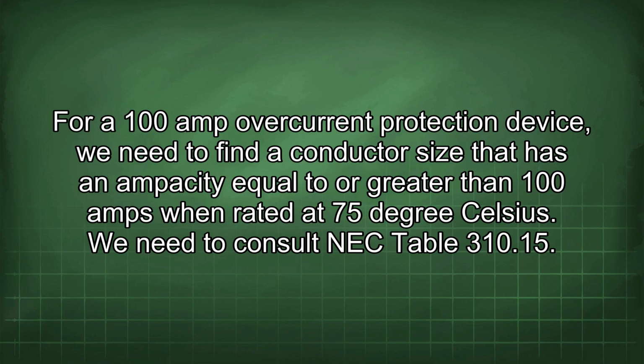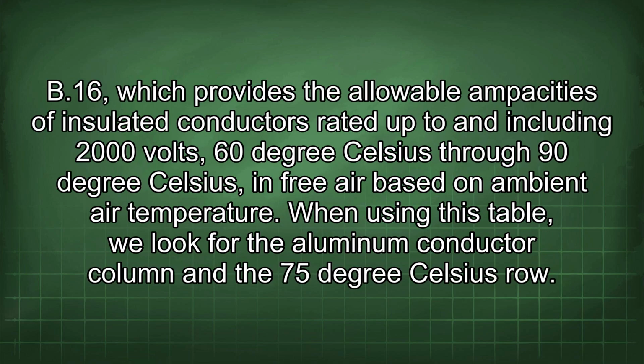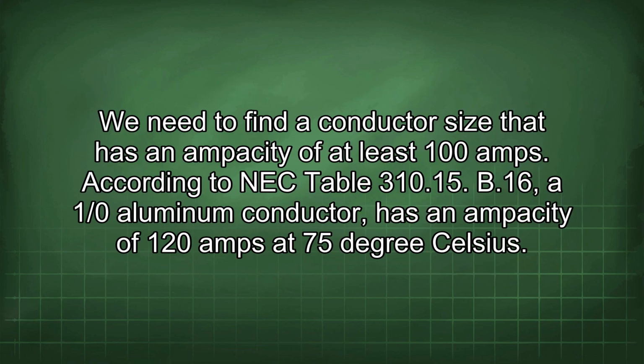We need to consult NEC Table 310.15(B)(16), which provides the allowable ampacities of insulated conductors rated up to and including 2000 volts, 60 degrees Celsius through 90 degrees Celsius, in free air based on ambient air temperature. When using this table, we look for the aluminum conductor column and the 75 degrees Celsius row. We need to find a conductor size that has an ampacity of at least 100 amps.